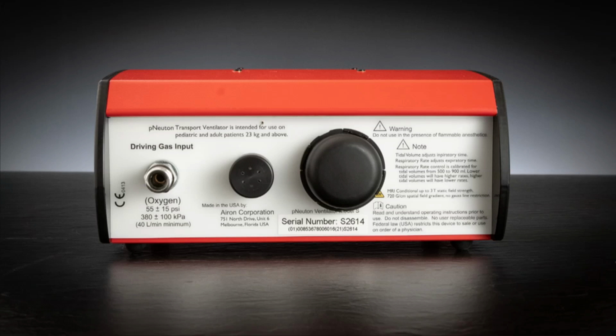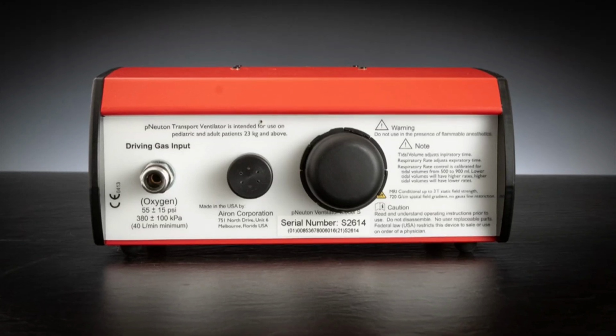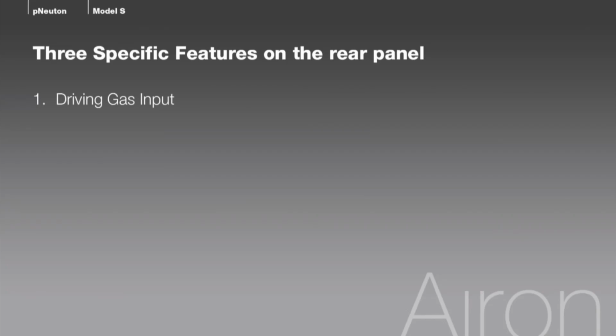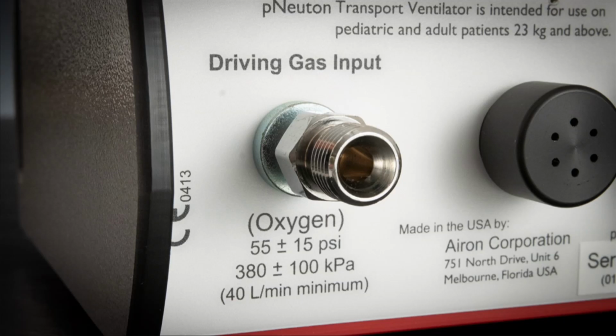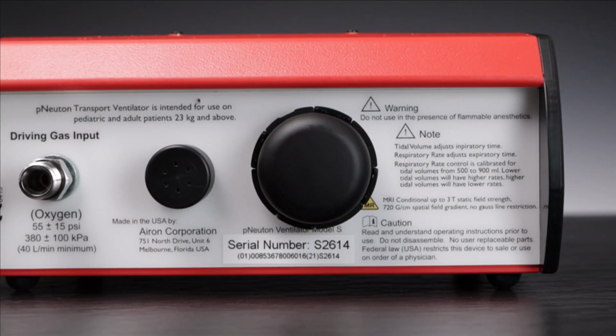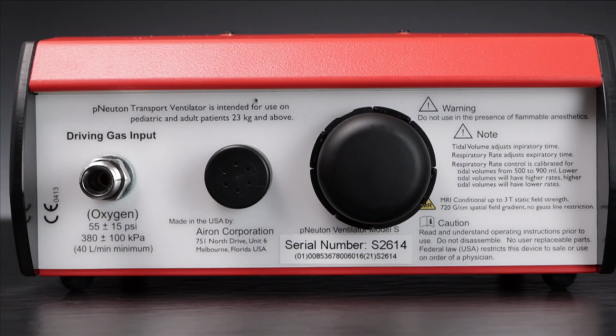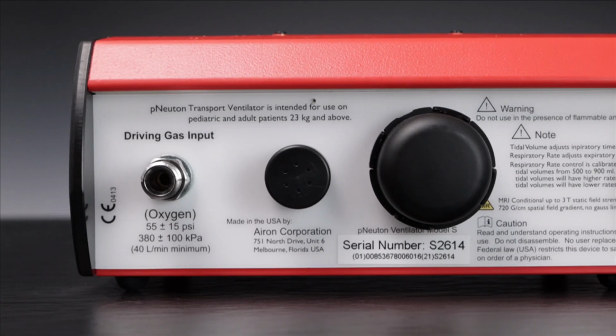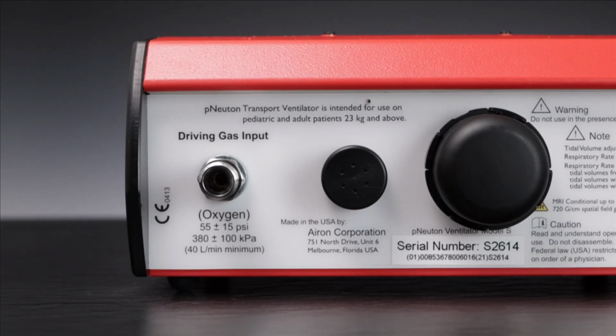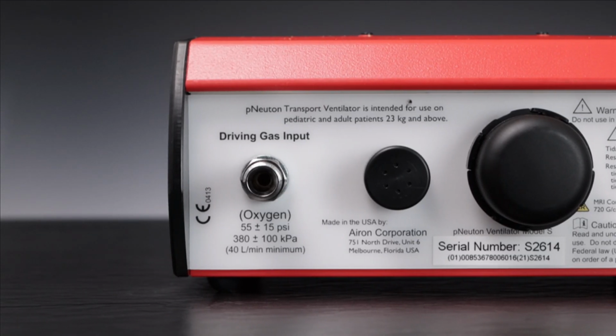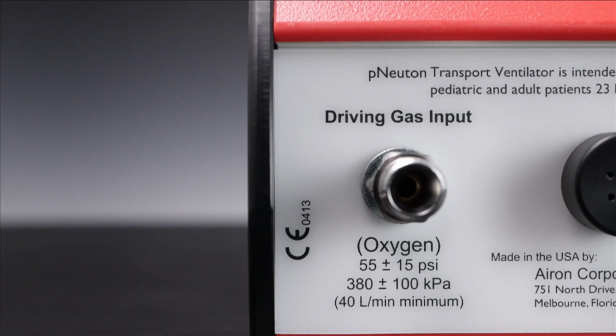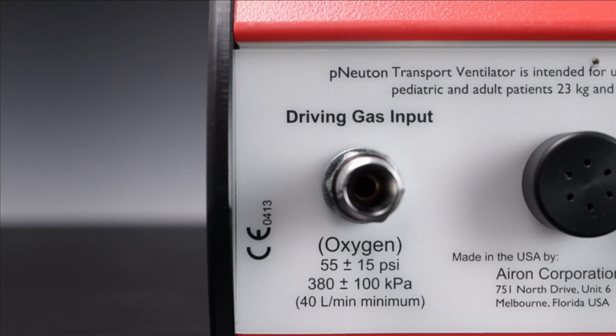Let's start our product in-service at the unit's rear panel and look at 3 specific features: driving gas input, audible alarms, and the air intake and filter. Driving gas input connection. The first item we will look at on the rear panel is the driving gas input connection. Keep in mind that the pNeuton Model S does not require electricity or batteries. Instead, the device runs on the ambulance portable compressed oxygen cylinder or the hospital's high-flow oxygen source upon transfer in the emergency room. The ventilator requires 55 psi with a minimum flow of 40 liters per minute.